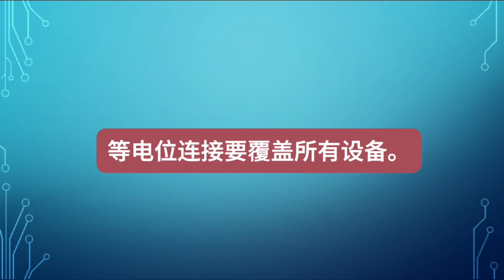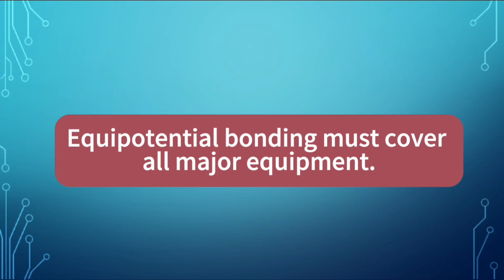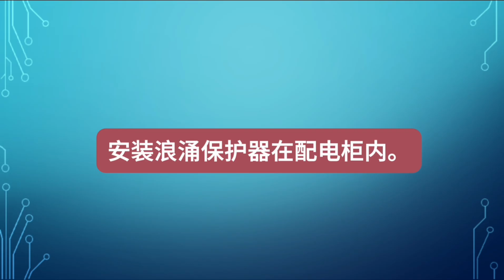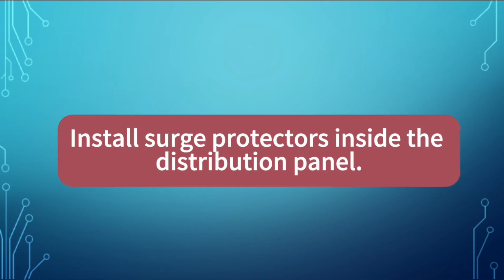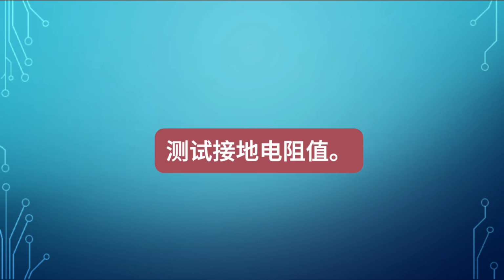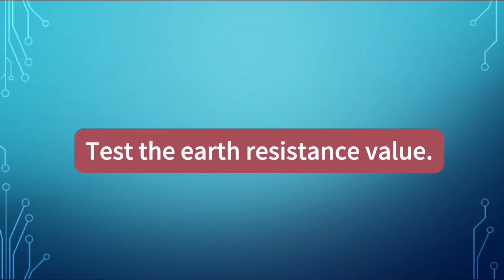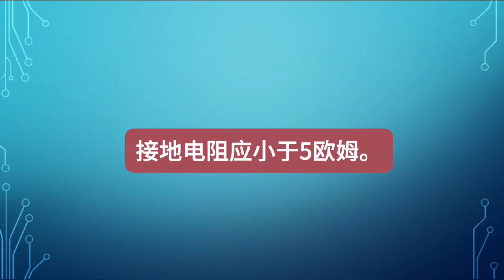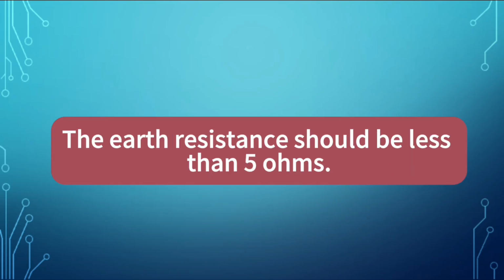Equipotential bonding must cover all major equipment. Install surge protectors inside the distribution panel. Test the earth resistance value. The earth resistance should be less than 5 ohms.